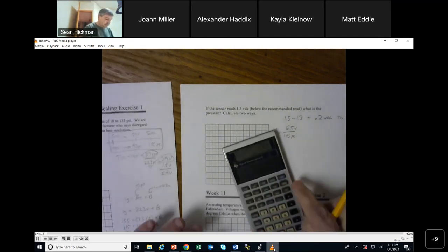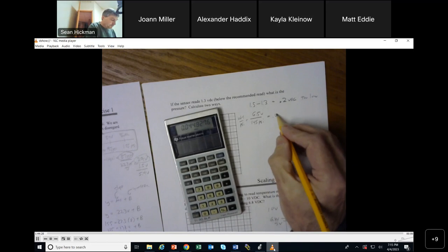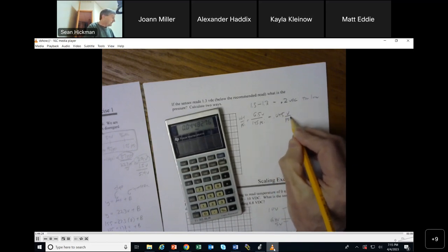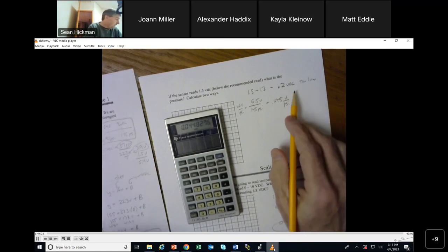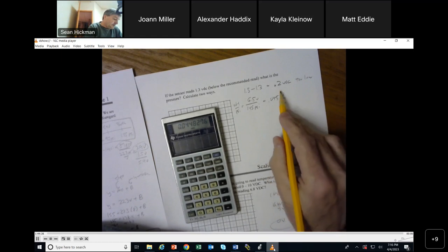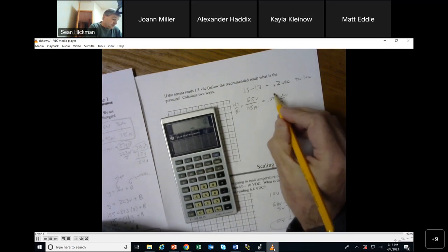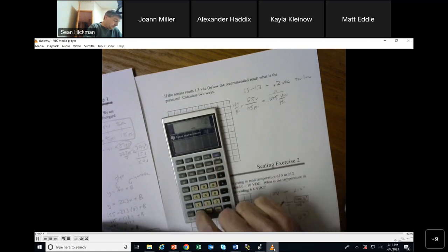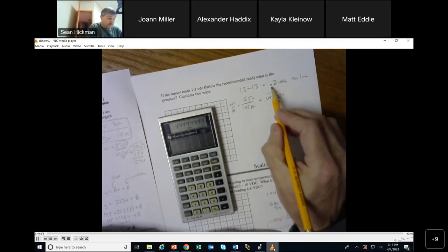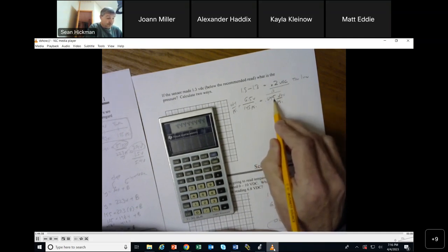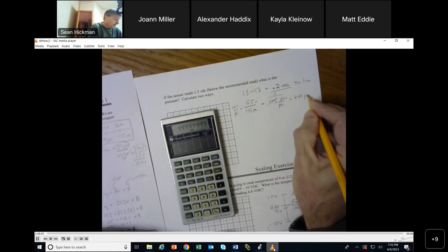So if I go 6.5 divided by 145 equals, I got 0.045 volts per PSI there, right? Okay. And so what do I do? I've got 0.2 volts. I can just divide this, 0.2 divided by 0.045 equals. I'm 0.2 volts under, and every 0.045 volts I gain a PSI, so 0.2 divided by that, I end up with another 4.44 PSI, okay?